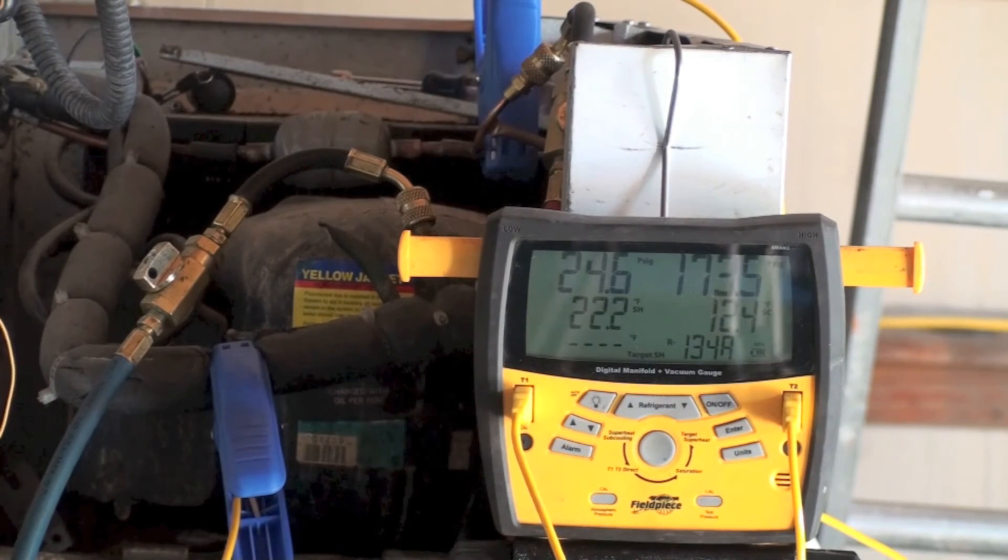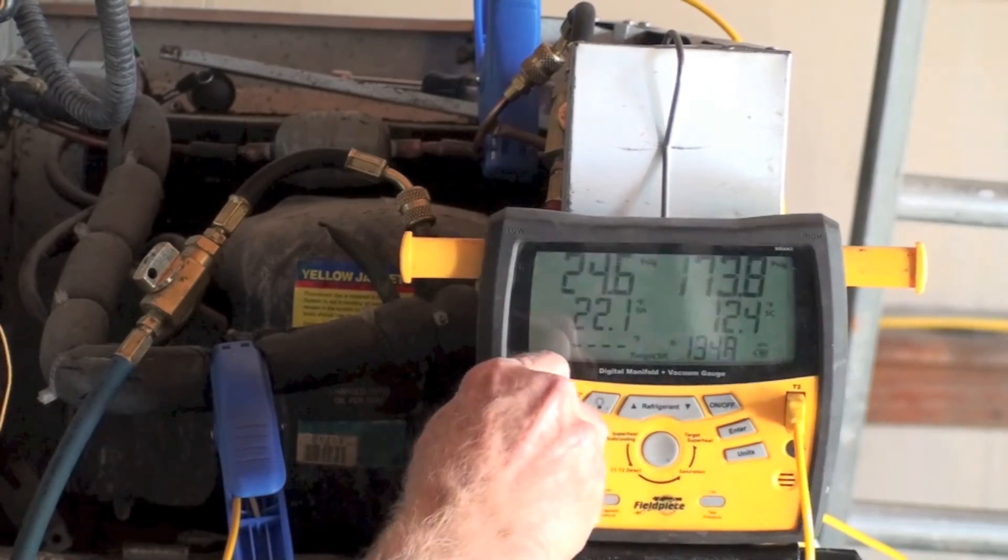surprisingly, an insulated suction line, you wouldn't think it would rise that much in temperature. And it doesn't even have the liquid line bonded to it. So, but it is quite a bit different. There's a lot different temperature between the two.